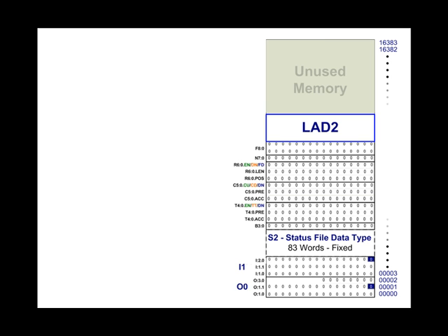For data files, you can create new files number 9 up through number 255, and you can have any data file number between without successive data files. You can have a data file 47 without having a data file 9 through 46. For program files, you can create ladder 3 through ladder 255. You can create a program file ladder 15, LAD 15, without program files 3 through 14.